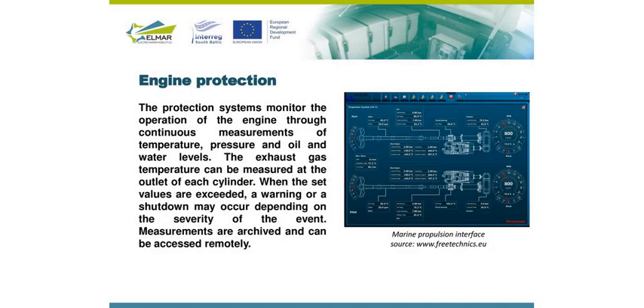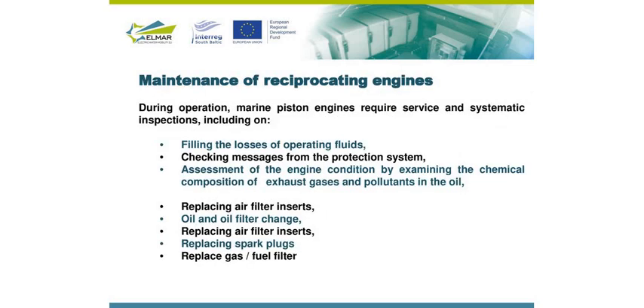An engine protection system is needed to control operation online and check for failures and, if needed, switch off the unit to prevent significant damage. Maintenance of reciprocating engines is also required. It is needed to fill the losses of operating fluids. The operator needs to check messages from the protection system.